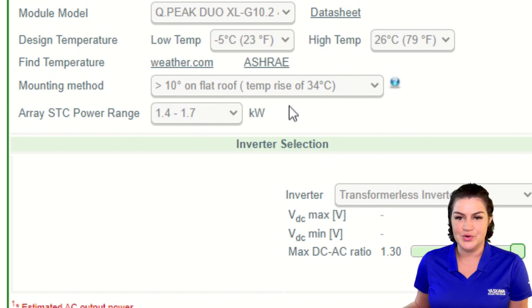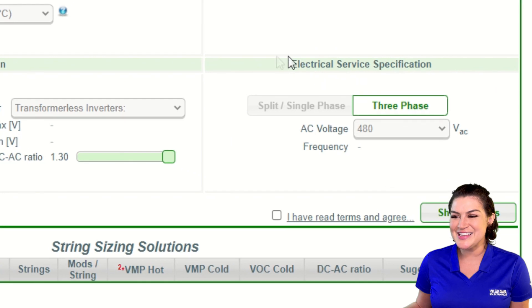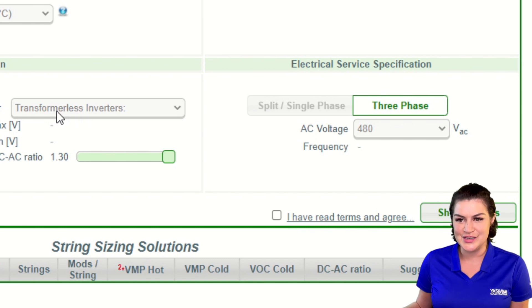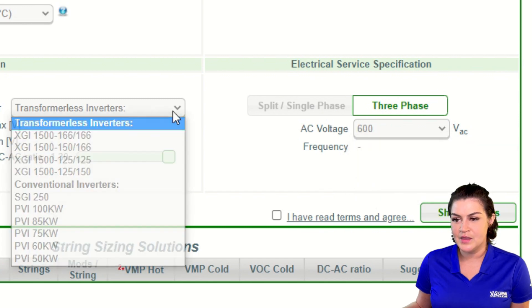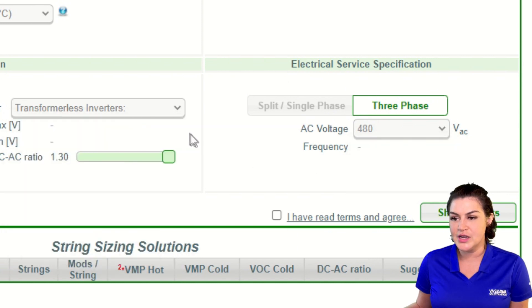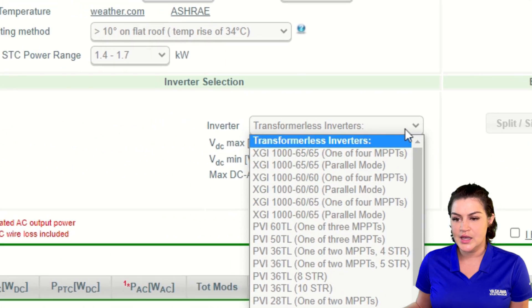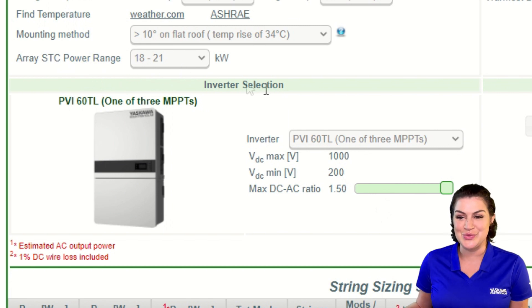I will ignore the array STC power range for now — just note this 1.4 to 1.7 default. Next is the electrical service specification. We do this first because it determines what inverters are listed under the inverter selection. We select a phase and then a voltage. I actually want 480 volts and this PVI 60 TL. Note that the array STC power range updated automatically — that's why we just ignored it earlier.